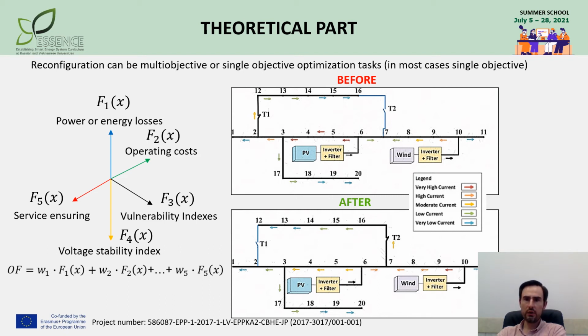In other words, there are several reasons why a grid operator may want to reconfigure the grid, and one or several of them can be considered at once. There are 5 most used objectives. The first one, minimization of losses. This objective is economical one, since nobody wants to pay for losses, and it's most frequently used.